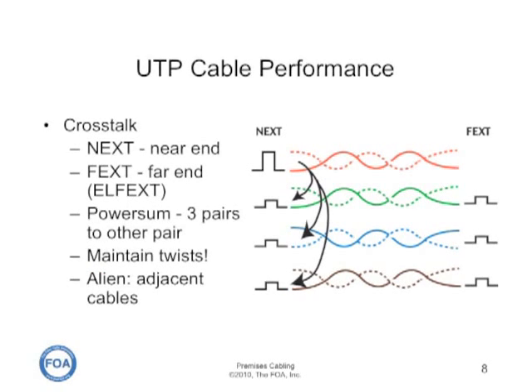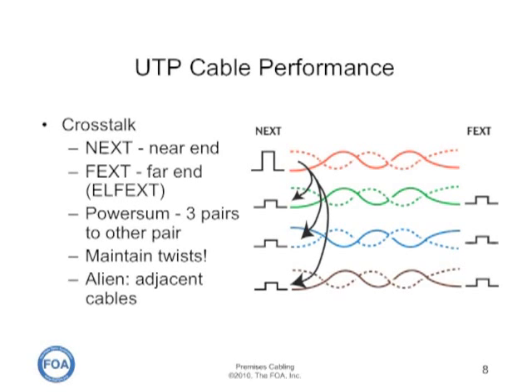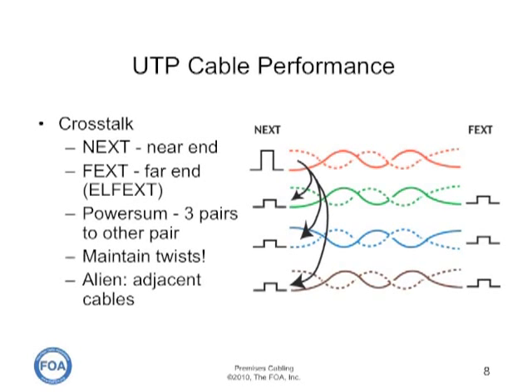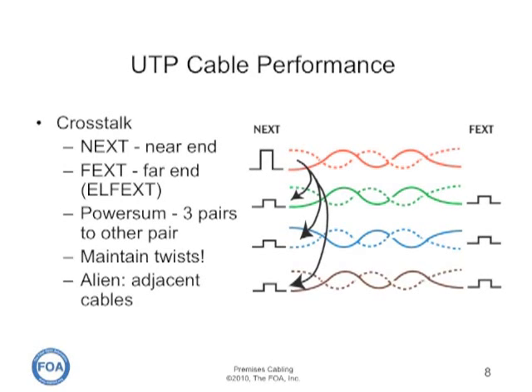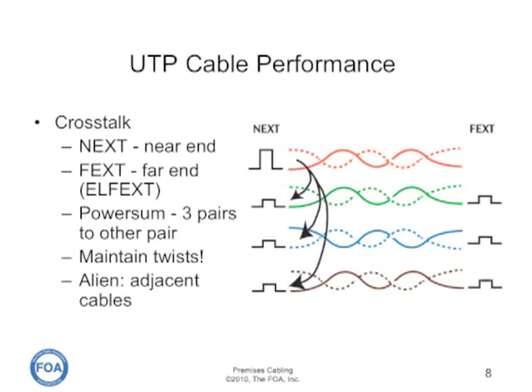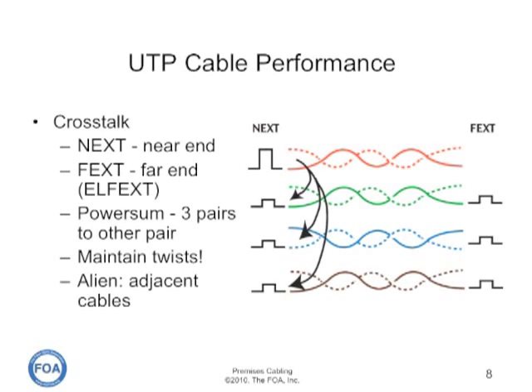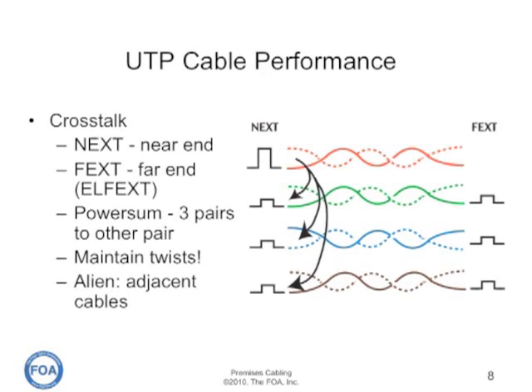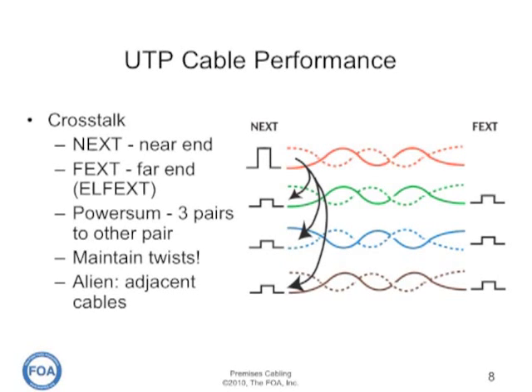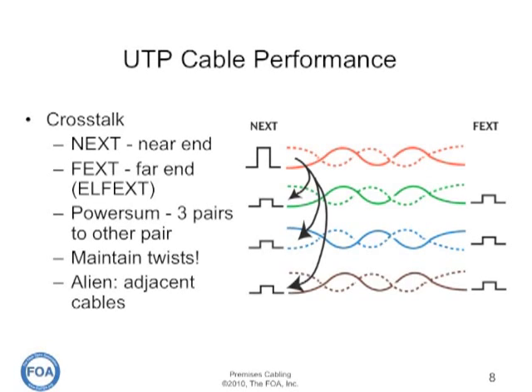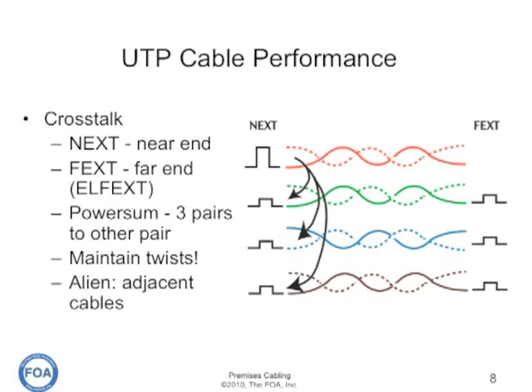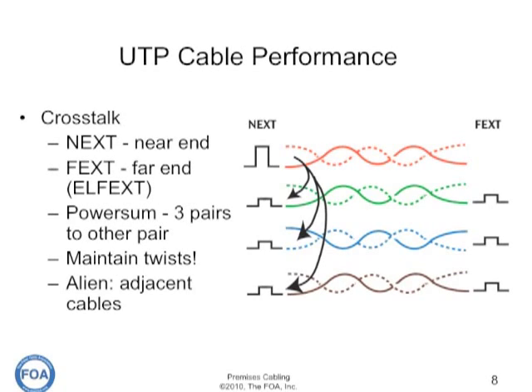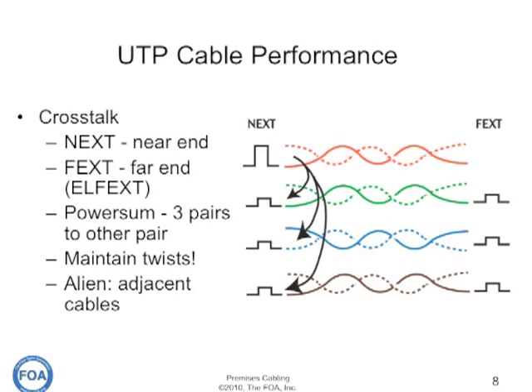Crosstalk refers to the coupling from an active pair transmitting signals to another pair in the cable. It's typically tested as NEXT on the near end and FEXT on the far end, because it's mainly at the connections where crosstalk is a problem. Power sum crosstalk, which has been required for all cables since category 5, refers to the coupling of signals from three pairs to the other pair. It's necessary because these cables now transmit signals on all four pairs at once. It's important at all the jacks, plugs, and punch downs to maintain the twists as close as possible, because that's where most crosstalk occurs.